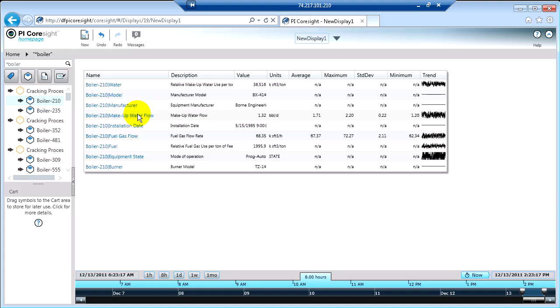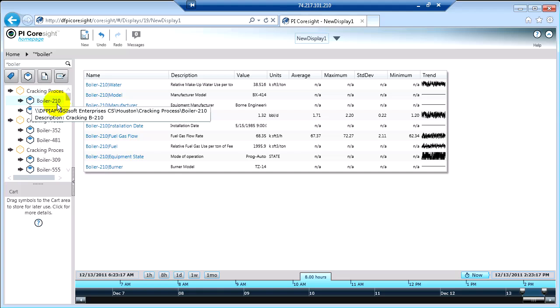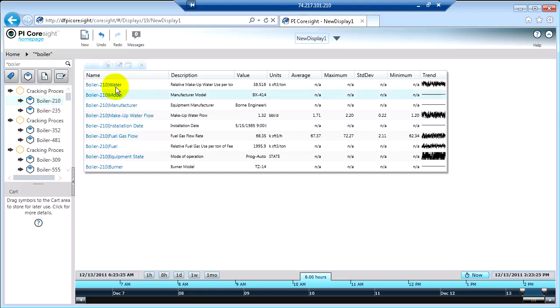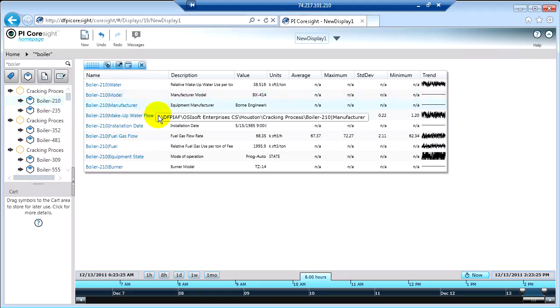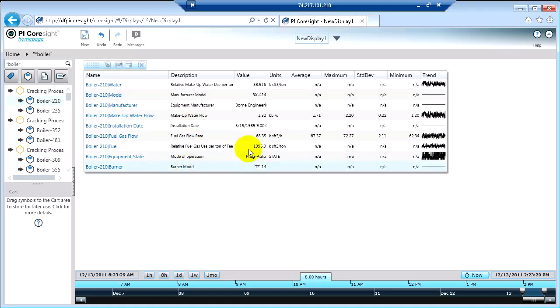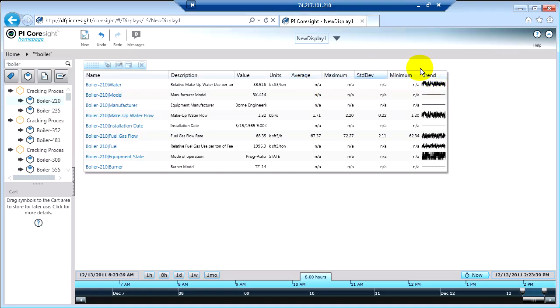PI Coresight is going out to the PI AF system and pulling in every attribute that's defined about that boiler. So I can see water, model, manufacturer, and so on. I can see the description of each of those items, and I can also see the current value, the engineering units, and then I can see average, max, standard deviation, minimum, and a sparkline trend. All of these calculations and the trend are based off of the display time range that I've selected — in this case, it's eight hours.